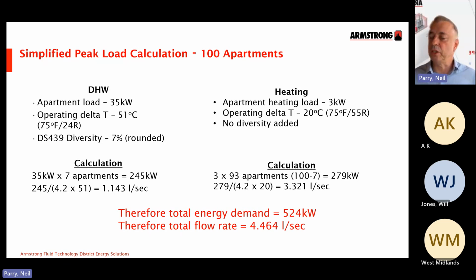Moving over to the heating calculation, we can see here I've used 3 kilowatts for the heating load at 20-degree delta T from, say, a radiator system. And I haven't added diversity, just to simplify the calculation here. But as I mentioned earlier, no problem in doing that if you need to. On the calculation side, then it's 3 times 93, because 7 of the apartments are on hot water load in this peak calculation. That gives you 279 kilowatts, and then underneath that is your flow rate calculation. Add those two together and you now have your kilowatt demand and your peak flow rate for the system. So we've used two separate delta Ts to calculate the single total demand.